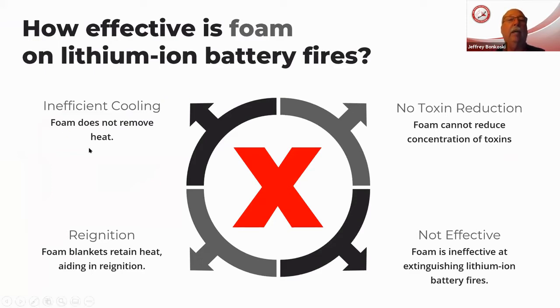I'm going to show a video demonstrating the ineffectiveness of foam to remove heat, because foam creates a blanket. What do we do at night when we get cold? Pull up a blanket. Same effect with foam - we're not doing anything to remove the heat. As far as reignition, the foam retains the heat, so it doesn't help. It doesn't do anything to remove the toxins from burning batteries, and it does nothing to encapsulate or affect the toxicity of the electrolytes.